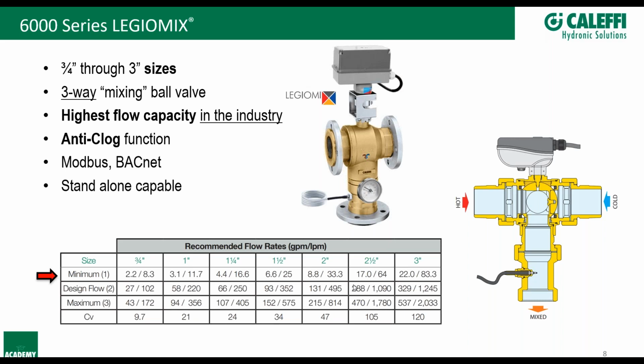One thing to be careful of is what pressure drop is acceptable in your building. Obviously if you're hitting that 190, you're going to be close to that 20 psi drop, and if that's not acceptable, I totally get it. Another great thing to think about is potentially doing parallel valves. If you were to take 2.5-inch models, that would get you really close to your 190 gallon per minute design.